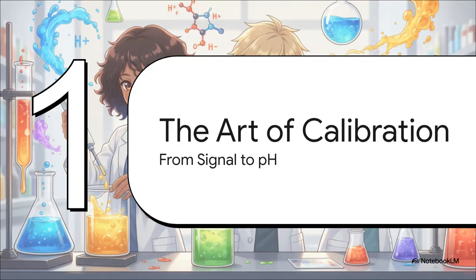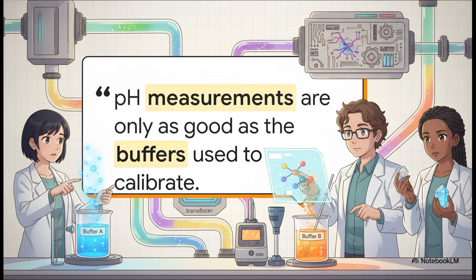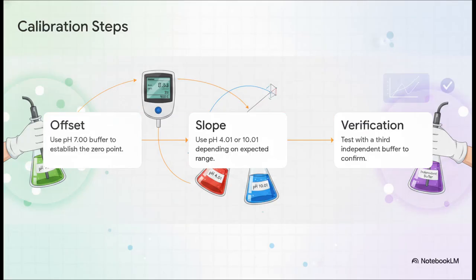All right, Section 4, the art of calibration. There's a famous saying, pH measurements are only as good as the buffers used to calibrate. And yeah, that is 100% true, because electrodes are basically just transducers producing a raw millivolt signal. They are flying totally blind without some context. That raw signal has to be converted into absolute pH values using precisely known standard buffers. If your buffer is wrong, well, your entire experiment is wrong. So here is the meticulous, non-negotiable procedure for doing this.